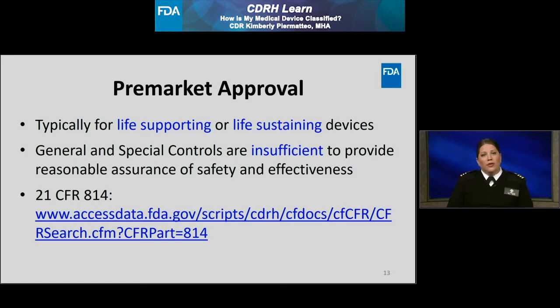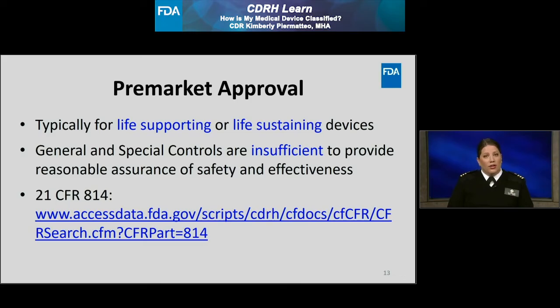Class 3 devices must obtain premarket approval prior to marketing. A premarket approval application, or PMA, is the most stringent type of device marketing application. PMA requirements are outlined within the Code of Federal Regulations, or CFR, under Section 814 specifically. Examples of Class 3 devices that require PMA are intraocular lenses and mechanical heart valves.